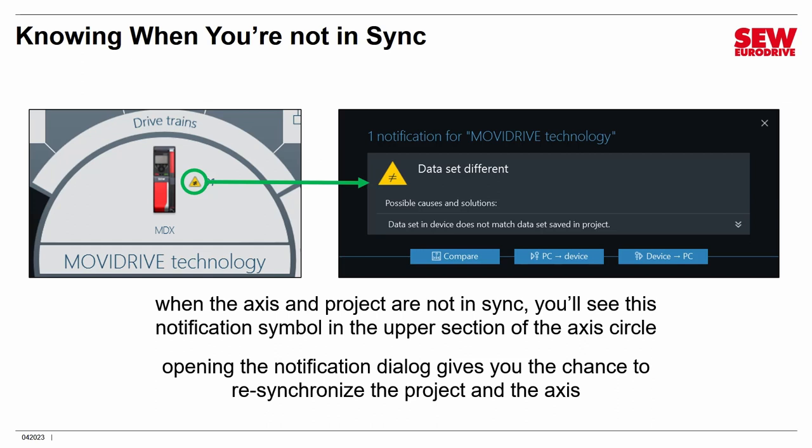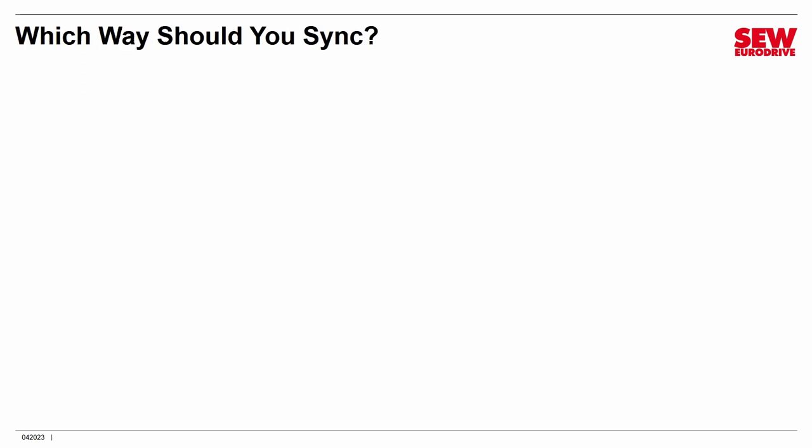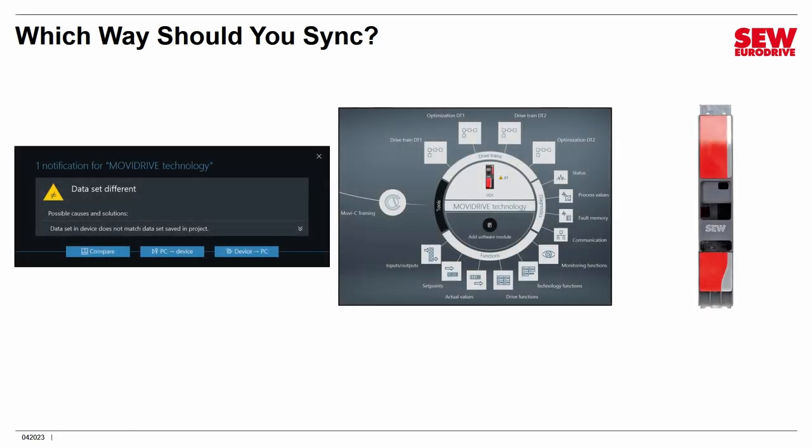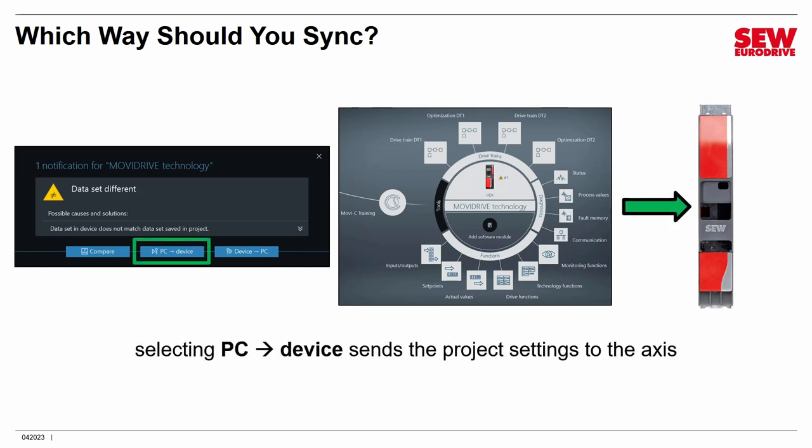And if you click that little symbol, this dialog box will pop up and say Data set different. In other words, something doesn't match. And this gives you the opportunity to re-synchronize the project and the axis to make them match. Now, here's where it gets complicated. There are two ways you can do this, and the outcomes are different. So I want to explain the difference so you know what you're looking at and which button to click. So which way should you synchronize? In other words, from the project to the VFD or the VFD to the project? Well, let me explain the differences first. If you select the first button, PC to Device, what it's going to do is copy what's in MoviSuite, what's in the project, in other words, into the axis, overwriting whatever is in the axis. So if your project is the thing that really needs to be dominant, then click PC to Device. It will overwrite whatever's in the axis, and then everything will be in sync, that little symbol will go away, and you can move on with your life.